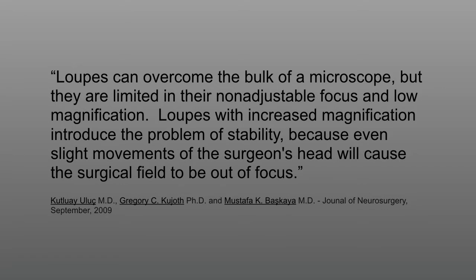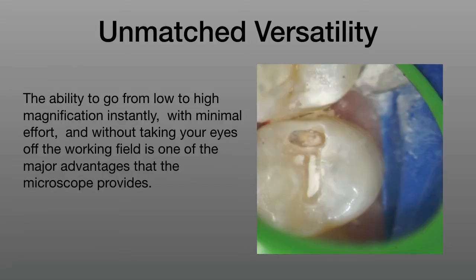Here's a quote from the Journal of Neurosurgery on loops versus microscopes: 'Loops can overcome the bulk of a microscope but are limited in their non-adjustable focus and low level magnification. Loops with increased magnification introduce the problem of stability because even slight movements of the surgeon's head will cause the surgical field to be out of focus.' During a procedure, you can switch the microscope from a large field of view with low magnification to a small field of view with high magnification. This provides unmatched versatility to go from low to high magnification instantly with minimal effort, without taking your eyes off the working field — one of the major advantages the microscope provides.